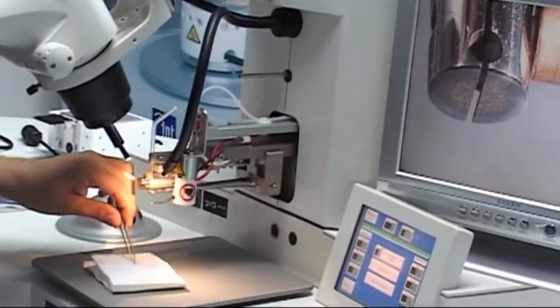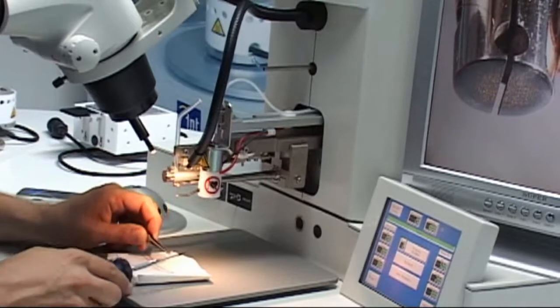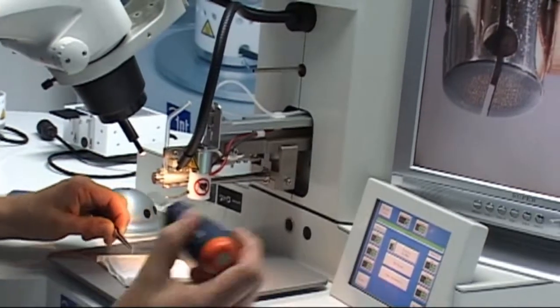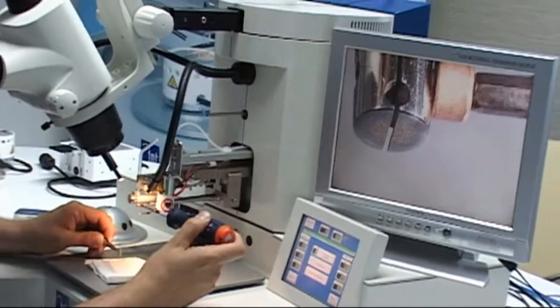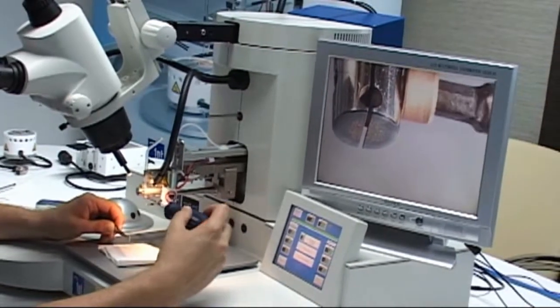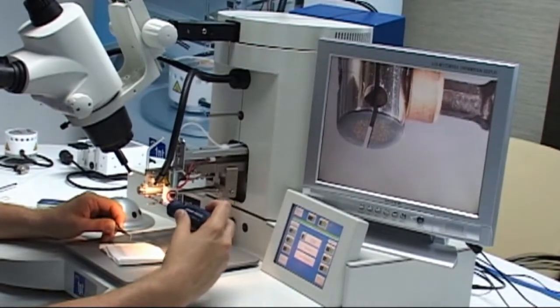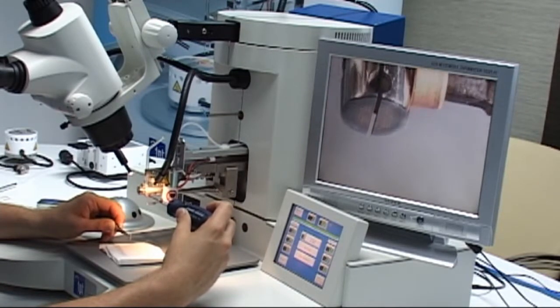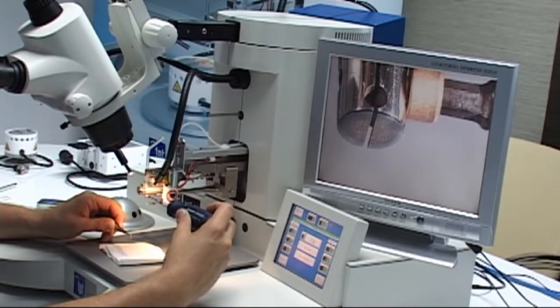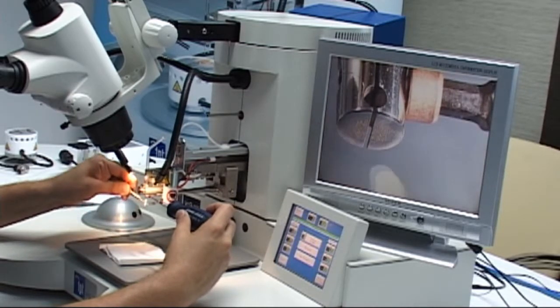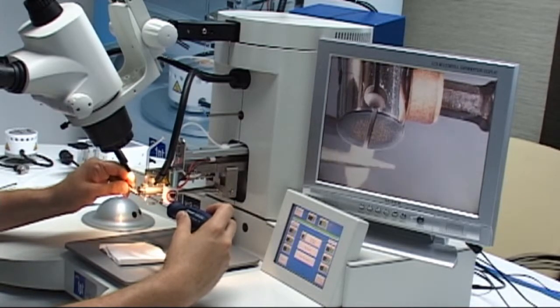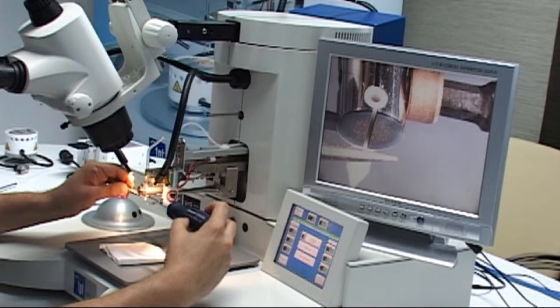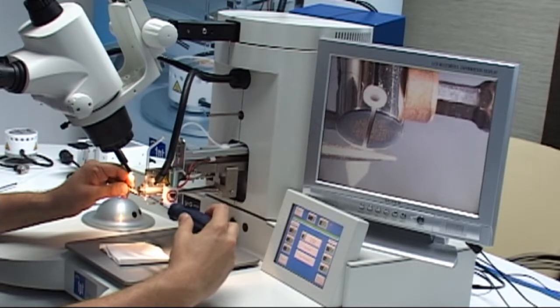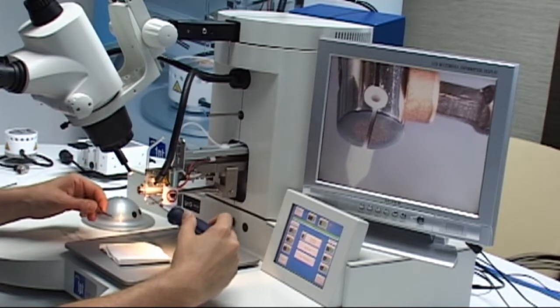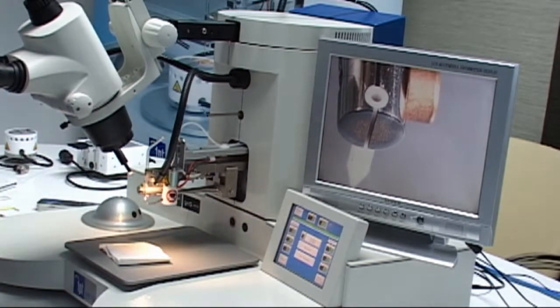So now with my left hand, I take the tool. With my right hand, I insert the torque wrench into the transducer screw, and you can see that prevents the transducer from moving. By that it's much easier to insert the tool until it's tight with the top of the transducer. Now I close it, you hear the click. Now the tool is installed with 35 centinewton meter.